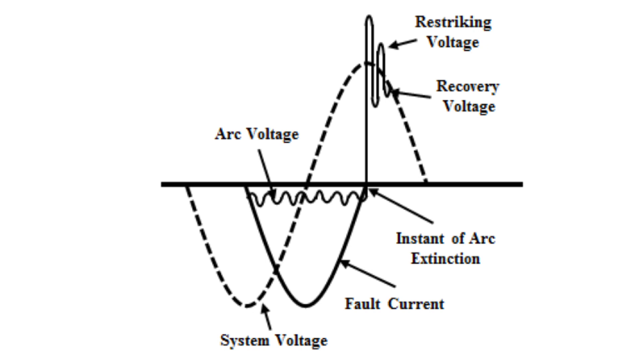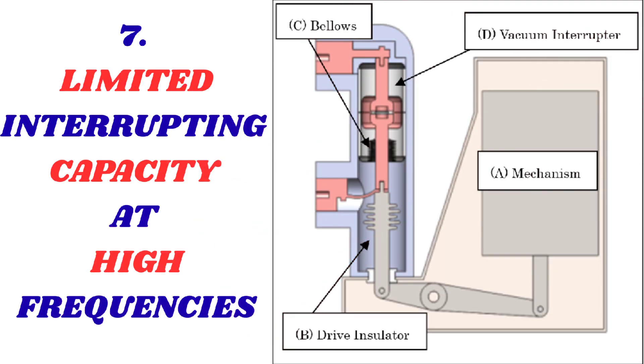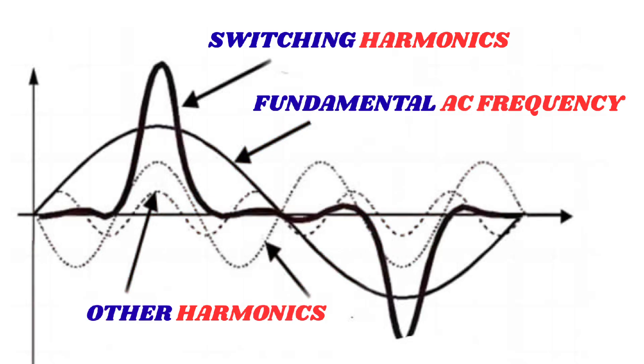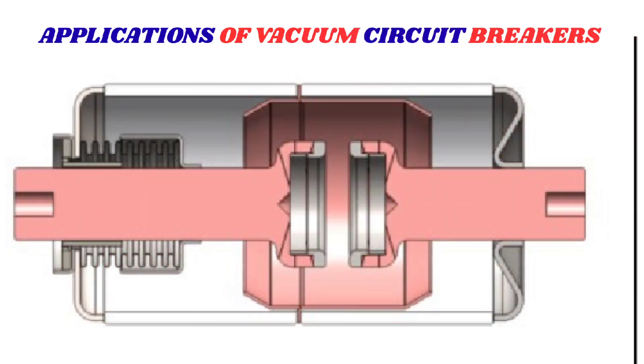The last drawback is limited interrupting capacity at high frequencies. VCBs may have limited interrupting capacity at high frequencies, making them less suitable for applications with high-frequency fault currents. This limitation is particularly relevant in applications with high-frequency harmonic content or switching transients. Despite these limitations, VCBs are widely used in medium-voltage applications due to their reliability, compact size, and low maintenance requirements.